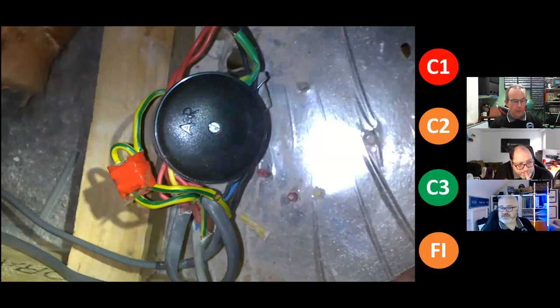I definitely think it's a C2 or an FI on this. I can understand why some people would say that if it's in a void space in a non-domestic building, they might think about authorised access and less risk. In domestic, though, we'd have to see to this, I think. Maybe an FI as well.